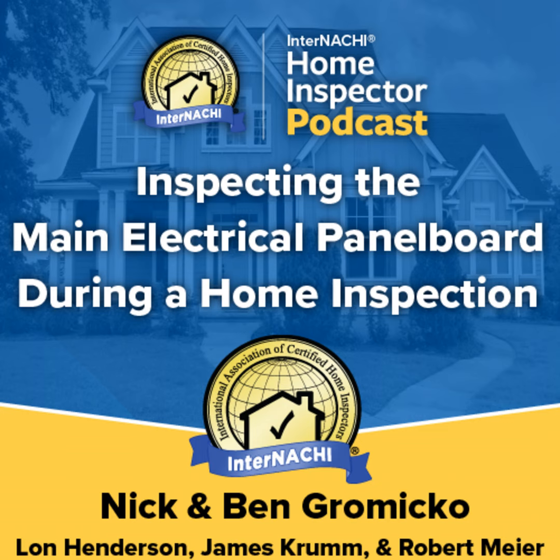Read the label on the cabinet front cover to identify the cabinet name and type. Check the condition of the dead front cover and for proper fasteners. Check specific identification for all breakers. Check for inspection stickers and dates. Check for unused openings, including knockouts. Identify the main service disconnect and rating if labeled. Identify the breakers in the off position.